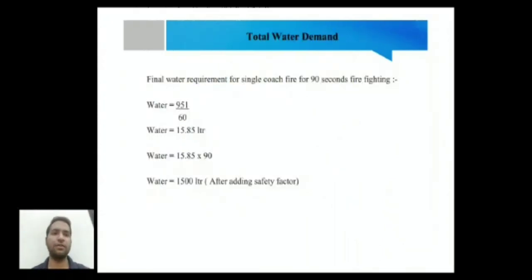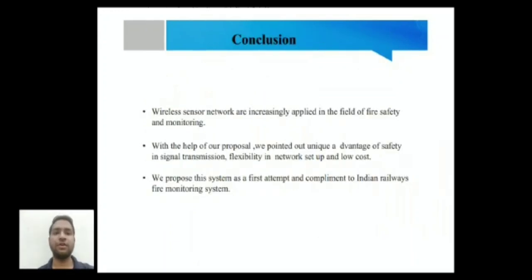In this last slide, we have calculated the total water demand to be stored in a railway coach for 90 seconds after adding safety factors, so that our total water requirement for 60 seconds is 951 lpm. For 1 second we divided it by 60, and it has come to 15.85 liters per second. After multiplying by 90, we calculated it for 1.5 minutes, which has come to 1500 liters. After adding all safety factors, this water is sufficient to extinguish the railway fire, which is stable and safe for passengers. In the next slide, the conclusion comes.